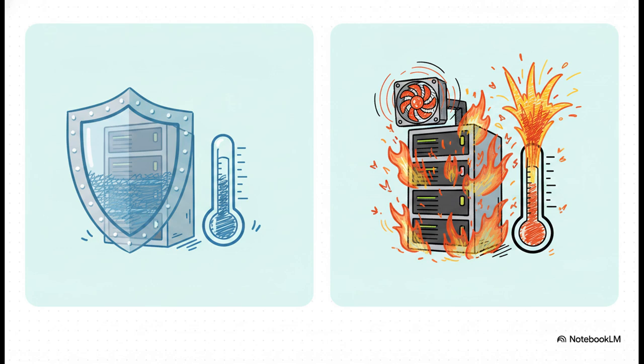Destratification. And let's look at the stark contrast here. When stratification is maintained, that stable 7 degree supply water reliably guarantees a safe zone for servers, which desperately require highly stable inlet air temperatures between 18 and 27 degrees Celsius. But when mixing occurs, that lukewarm water simply cannot absorb the immense thermal load fast enough.